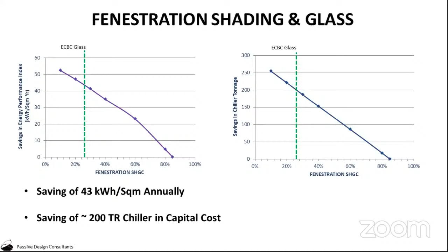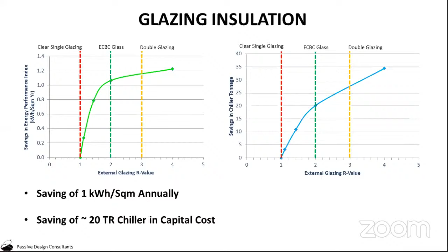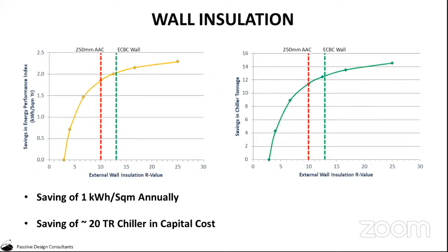By changing the glass type from single to double, many people think that changing single to double glass has a lot of impact. Well, not for this building. We analyzed that saving was very minimal, only 1 unit of electricity per square meter, and only 20 tons of cooling load was reduced by using DGU, by double glass. Additionally, we also checked what will be the benefit of insulating our walls, and again realized that because it has very minimal wall area, only 1 unit of electricity per square meter would be saved, or approximately 20 ton of chiller cost.